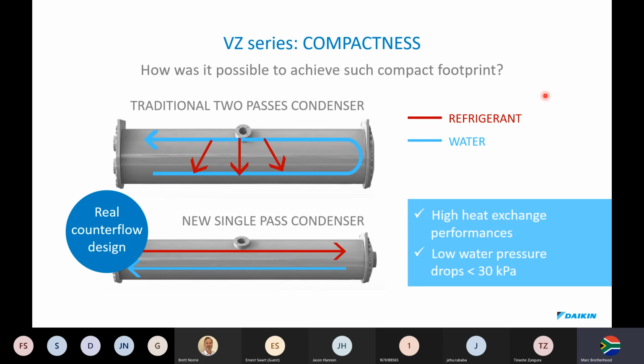So how is it possible to achieve such compact footprints? Here we see, mentioned earlier on, a traditional 2-pass condenser. The hot gas would come in from the compressor, and it would fragment at multiple angles. With a single pass condenser, we don't just chuck hot gas in, we put the gas in and we let it flow counterflow. So you'll see there's a lot more time in contact with the water. Okay, so there's the refrigerant and water.